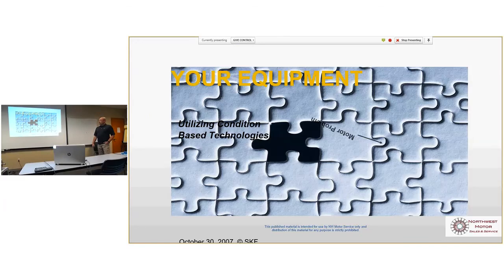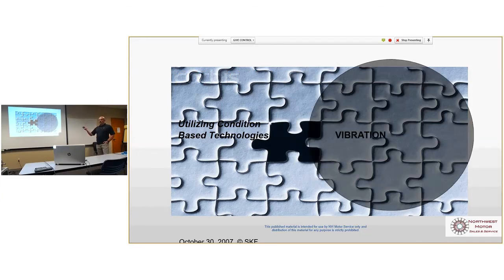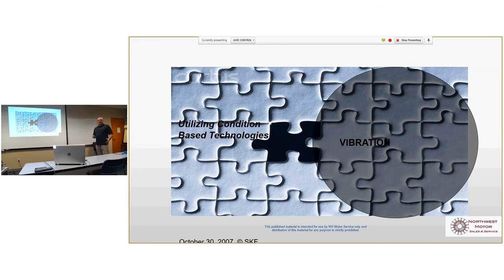So, motor testing, there are lots of different technologies out there. We're going to be focusing on the electrical side of it with this presentation. There's vibration analysis, which is really strong for the mechanical side of things. It's another reason we like to see the bearing information on those nameplates, because if you have a good vibration program, you're entering in the bearings for the motors you're doing the vibration on, and you can tell if you have bearing issues before they actually fail on you.